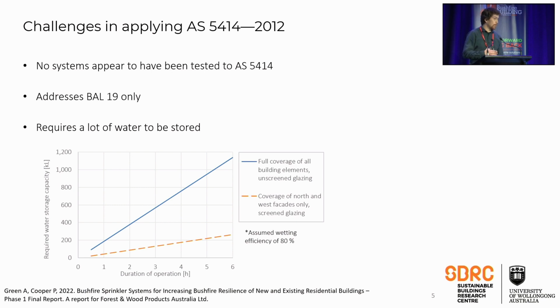So you're looking at between 20 and 100 kilolitres for just the minimum 30-minute duration of operation that the standard requires. But if you want to operate the system longer, for example to evacuate early, leave early, operate the system before you leave, you might need several hours of operation, in which case you're looking at hundreds of thousands of litres.